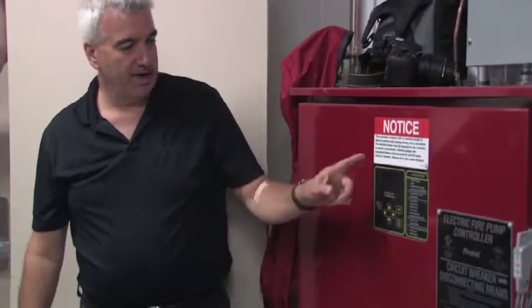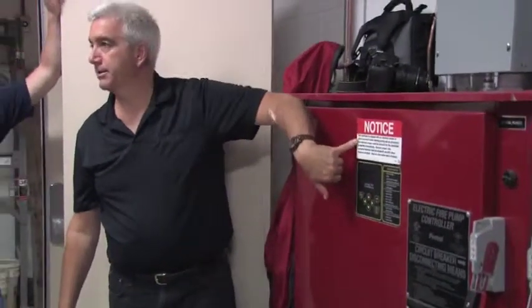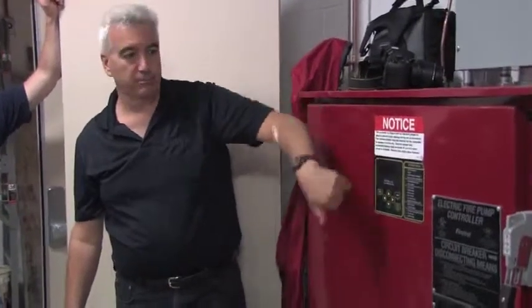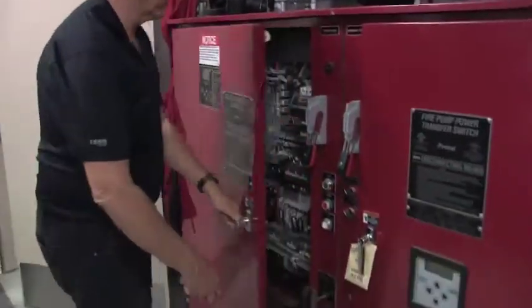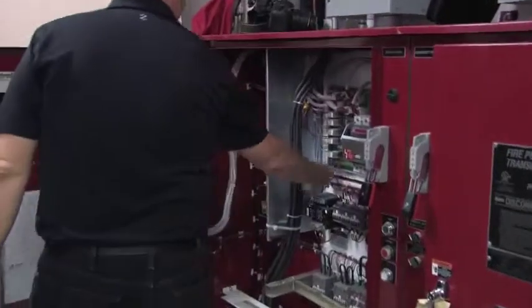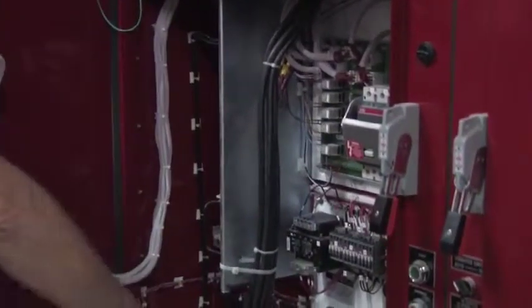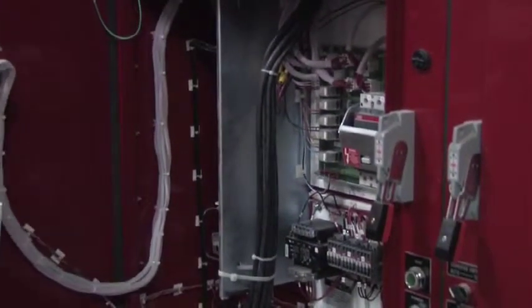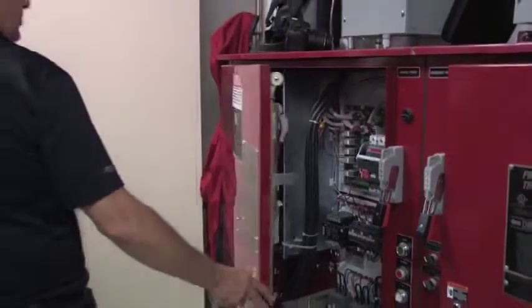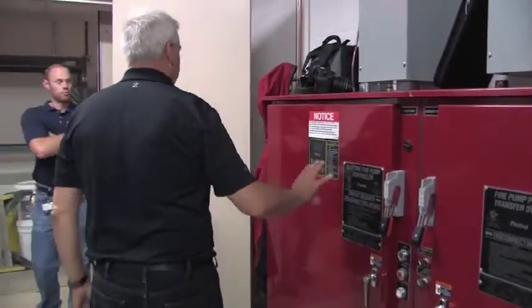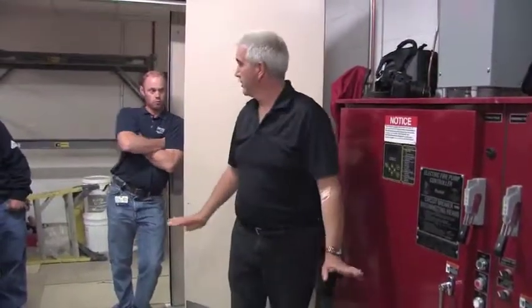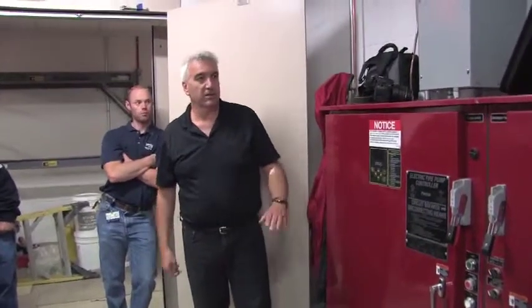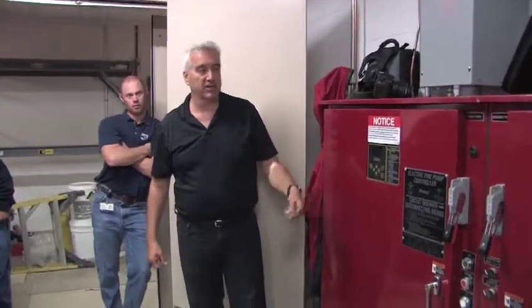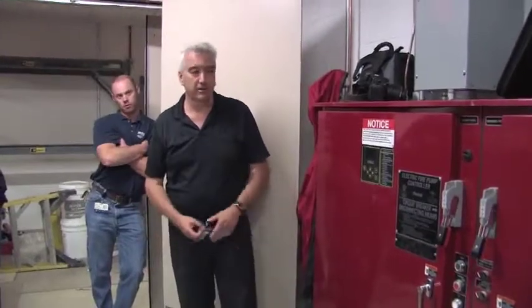Right now you'll notice it has a big sticker here that tells us the interlock jumper is still in place. That's just a little jumper on this main circuit board, so that if somebody were to come in here and flip a switch on without taking into consideration what the system pressure is, this will not start on a pressure drop at the moment. That's all it means. Once this is in for its final operation, that jumper will come out and stay in the bottom of the cabinet. It's just a safety.